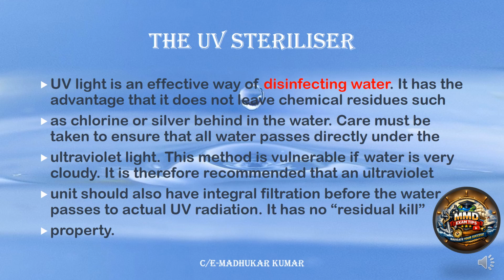This is something which requires frequent cleaning of the quartz sleeve and the ultraviolet lamp, and the ultraviolet lamp needs to be replaced. As the intensity comes down, the rate of killing microorganisms and bacteria also comes down. So that also you have to think of.